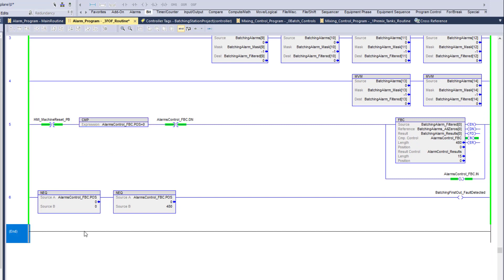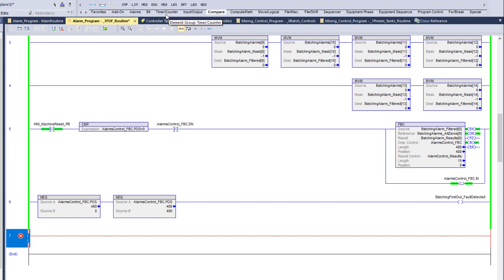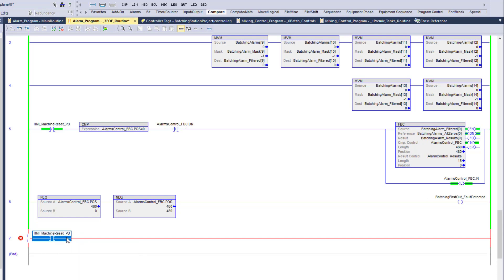If you're concerned about timing, you can add a second rung below. If the position is equal to zero or 480 — the full length — you can come in and do a one-shot and clear the control as well. In our scenario we don't necessarily need this, but in large-scale systems you may need to put this in.